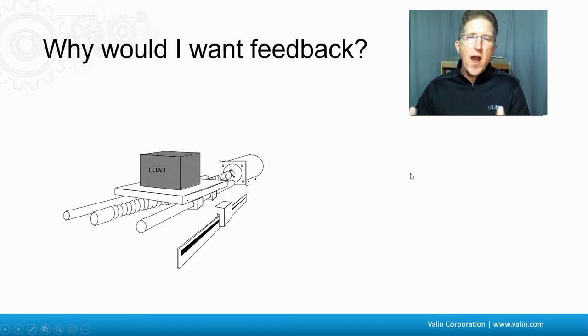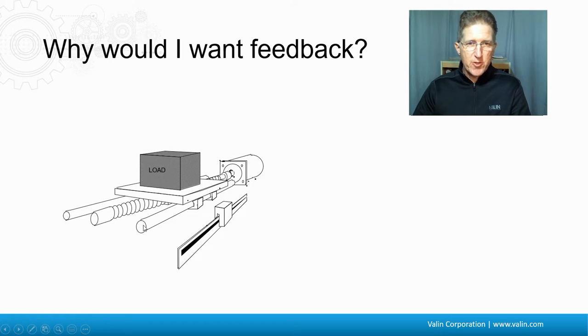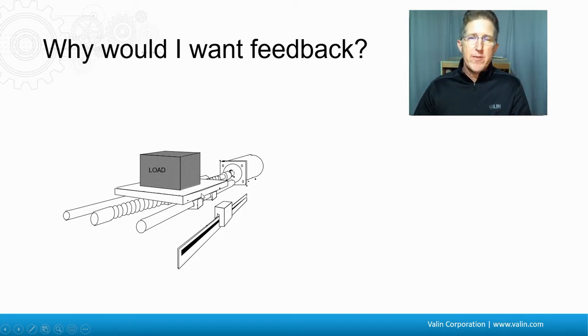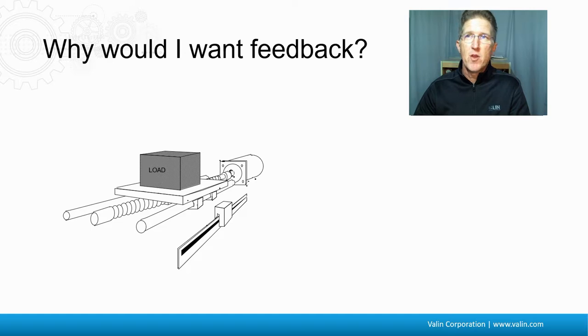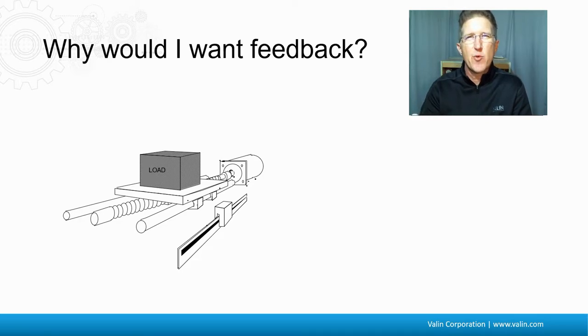That helps us ask the question: why would you want feedback? Let's say you put a motor on a ball screw, and you have bearings carrying the load. You can put a linear scale along the side, and a read head runs along the scale attached to the carriage, providing feedback. Maybe you're worried about whether your load is actually getting to the location you're telling it to, or what happens if the coupler slips or breaks. Or maybe you're concerned about whether your ball screw actuator is precise enough and you want a little more precision out of it.